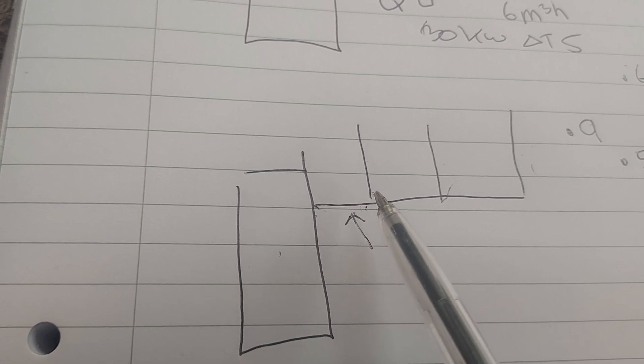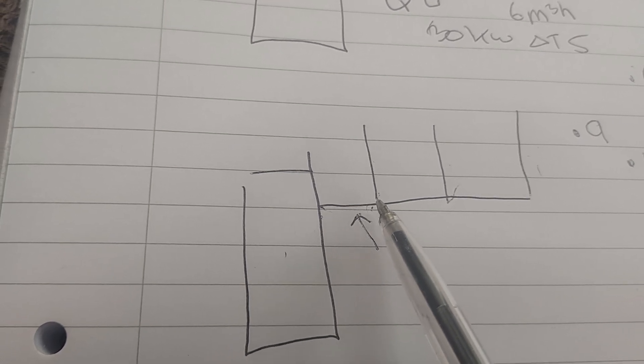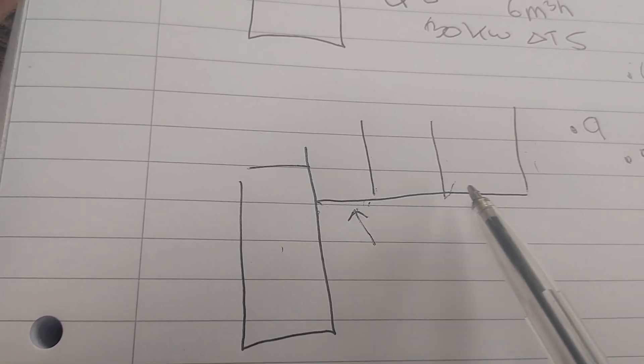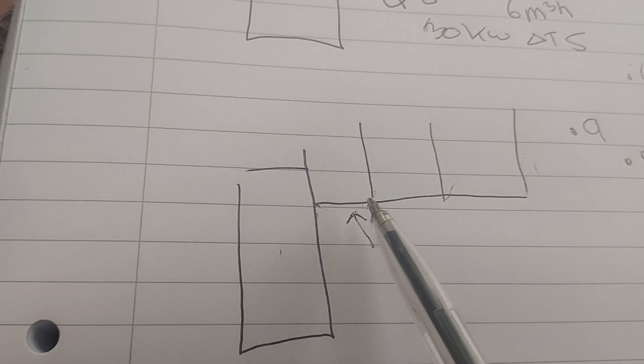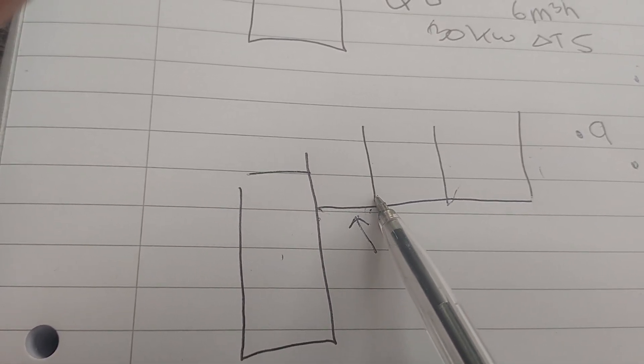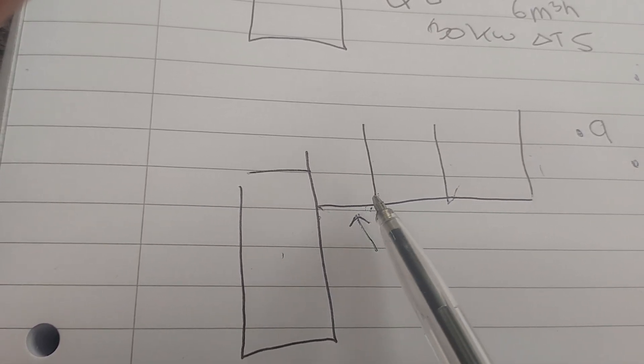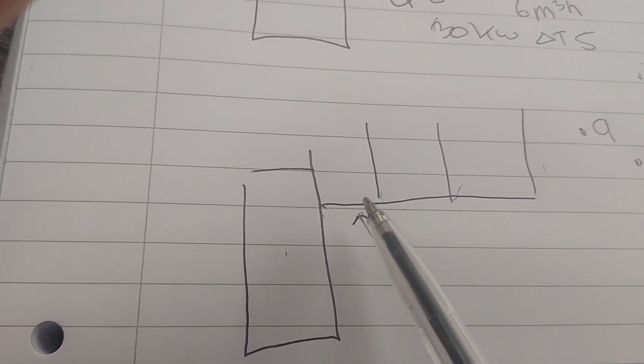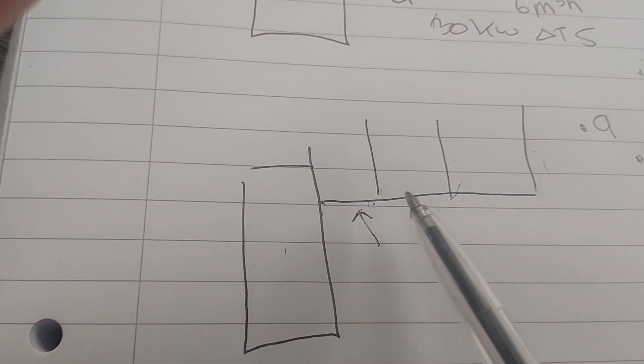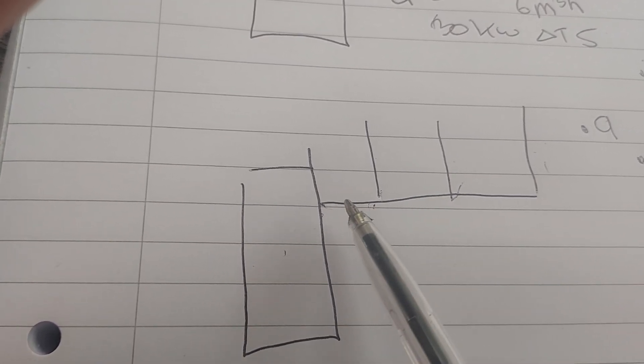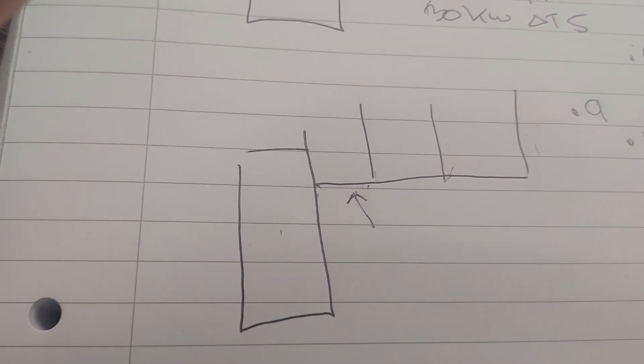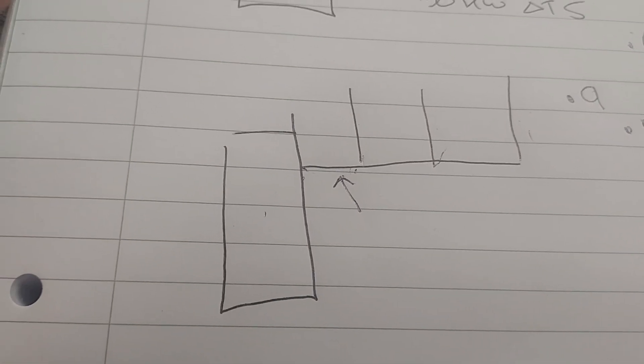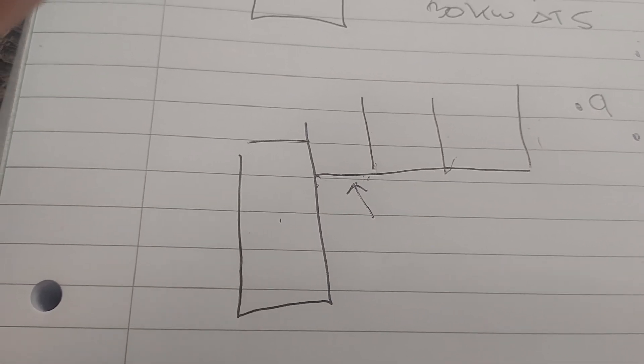But technically it's correct. However, this length of pipe is very very short, and the shorter these are, the less influence the pipe size has over the pressure difference. So I don't know how important it is for me to get that 35mm in there. I'm doing it because I can, but I think if you've done these before and you didn't know about this and you'd put 28 in here, I don't think it would be a significant impact on your system.